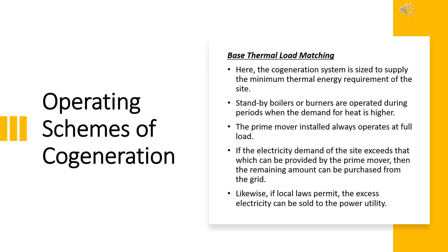The second scheme is base thermal load matching. The co-generation system meets the minimum thermal energy requirement. Minimum electricity is generated accordingly. Standby boilers and burners are operated during periods when the demand for heat is high, ensuring the minimum thermal energy requirement is always met.